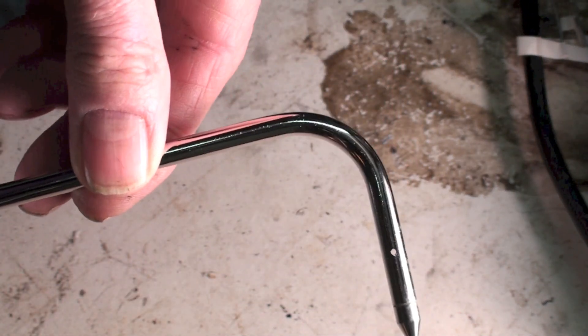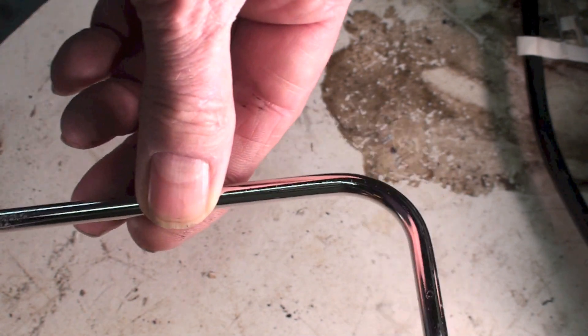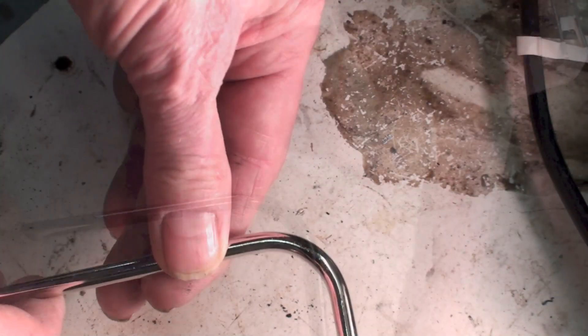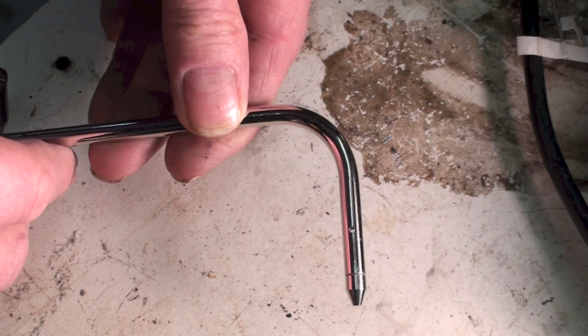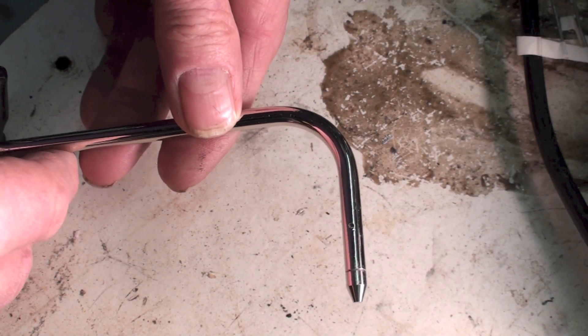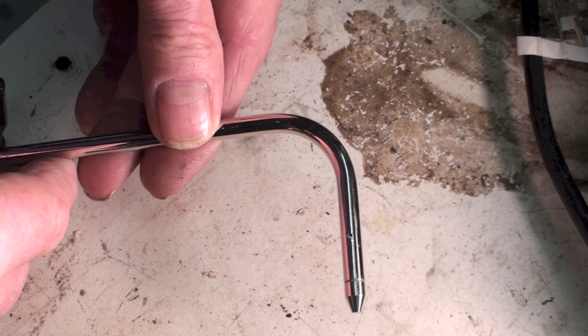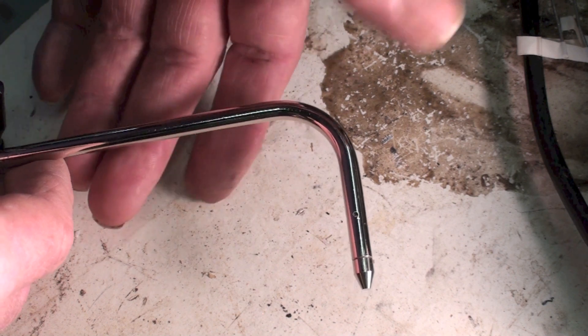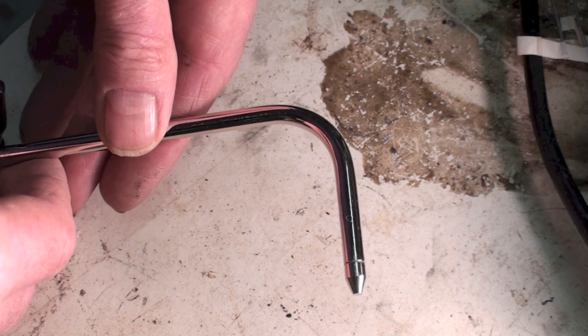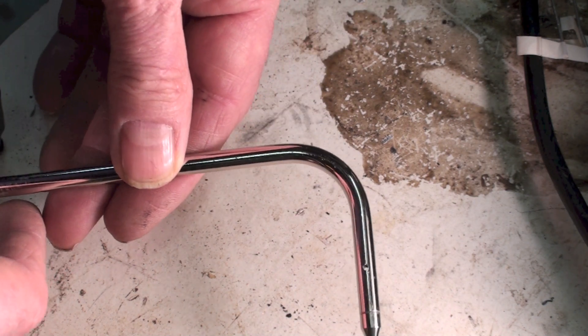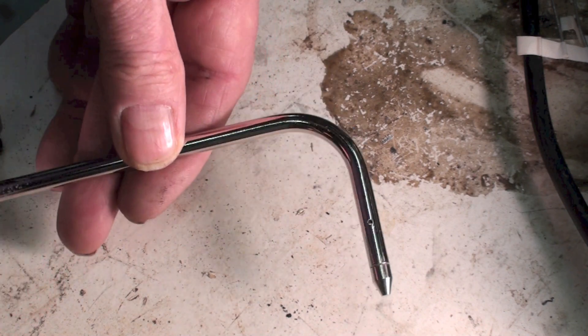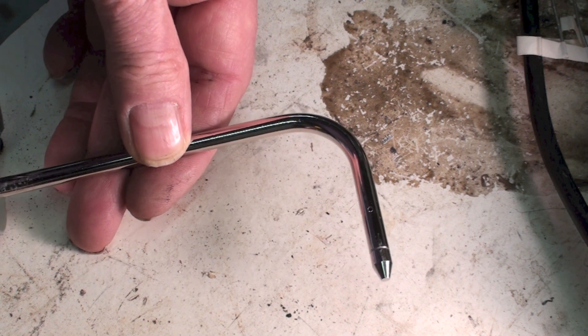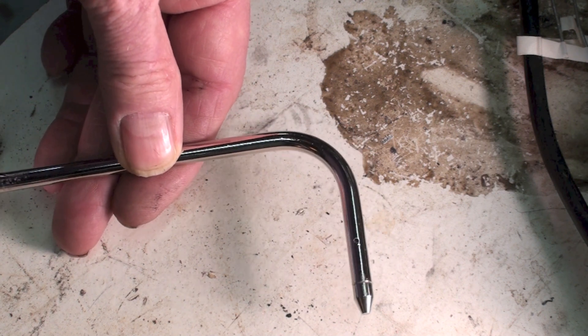This is supposed to be set up so the airflow is going this way. On these low velocity ductwork systems it doesn't make a lot of difference - sometimes you can just put the hose in there and it still reads about the same. But I do use these things because they're convenient, and if you had higher velocity you'd probably want to use these.